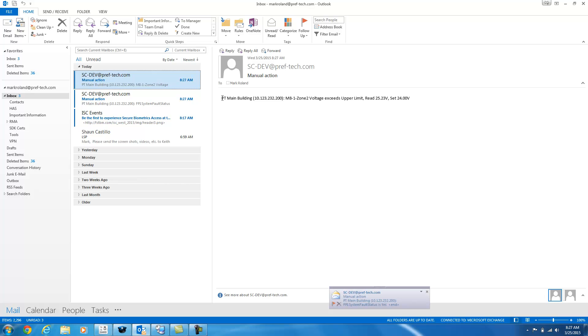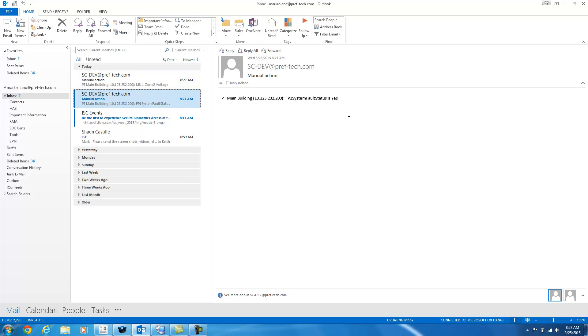So it tells me here this is the device, PT Main Building, its IP address, which zone it was. So it's on MB-1 zone 2, and then what happened? It exceeded its upper limit. It was read at 25 volts. It was set for 24. I also got one for a fault status indicating that the board is now in a fault status, so it says yes here.